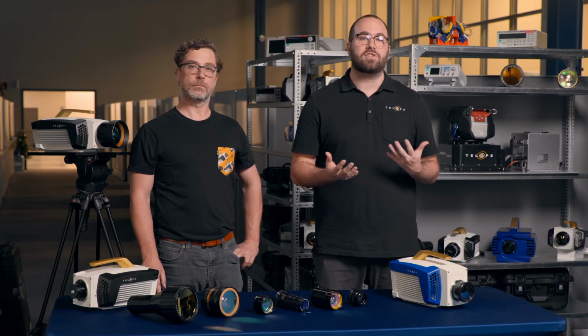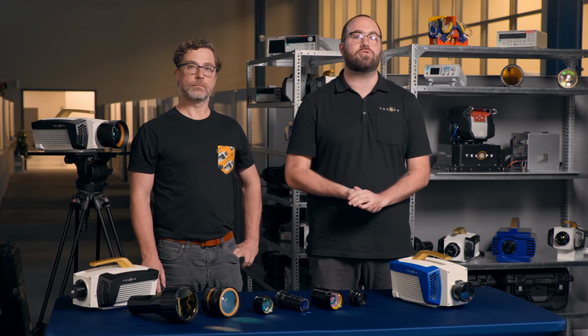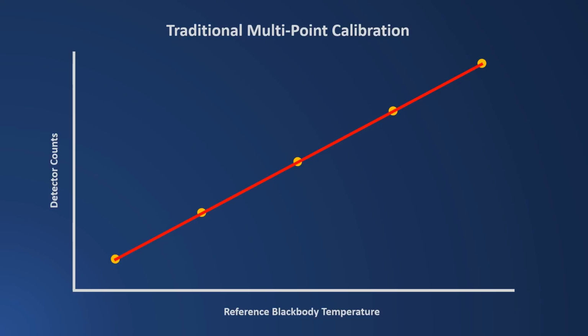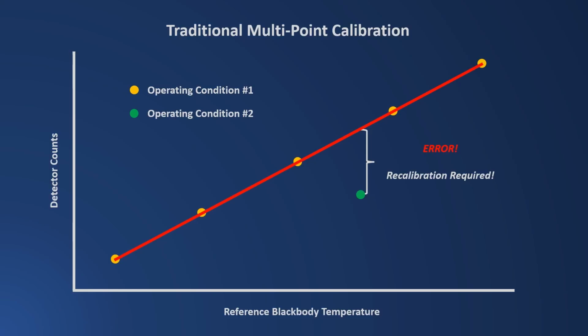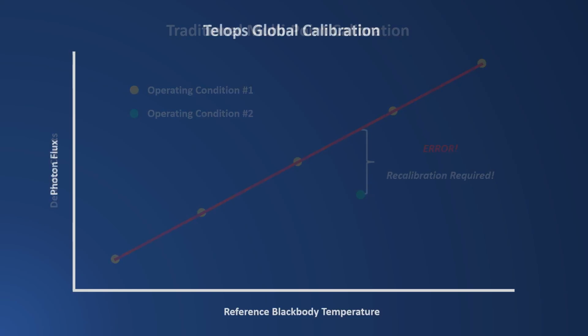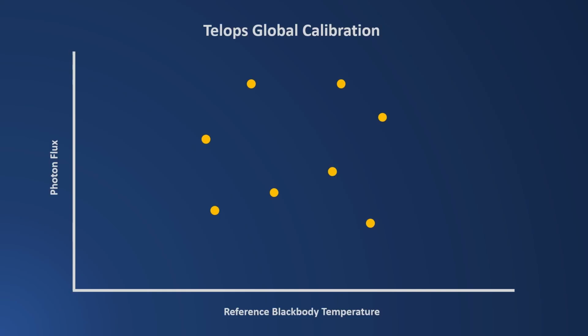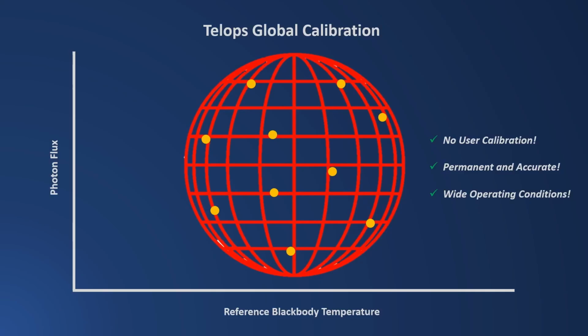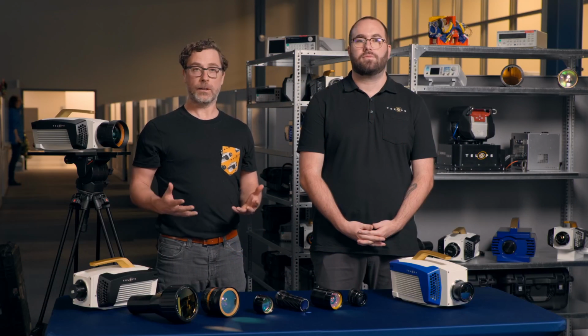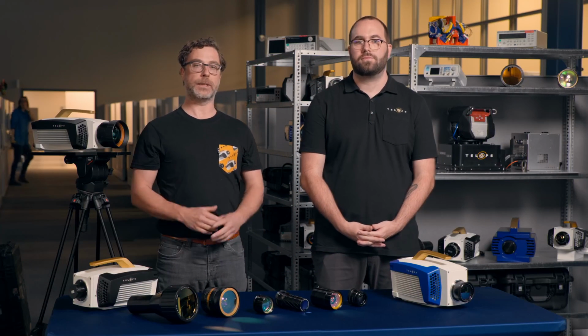But sometimes our experiment calls for us to change these parameters to optimize the measurement. If we're using a multi-point calibration, changing any of the camera's operating parameters will necessitate recalibration of the system or accepting a reduced accuracy performance. In contrast to standard reference-based multi-point calibration, Telops systems offer proprietary onboard global calibration, which allows the user to modify any and all the instrument parameters without the need to recalibrate.